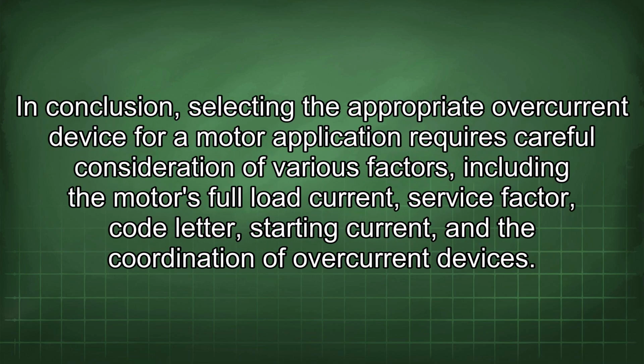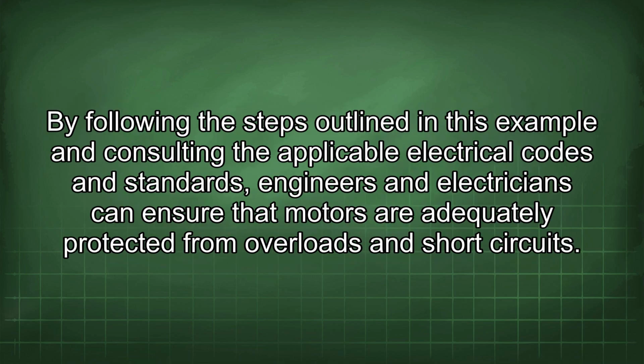In conclusion, selecting the appropriate overcurrent device for a motor application requires careful consideration of various factors, including the motor's full load current, service factor, code letter, starting current, and the coordination of overcurrent devices. By following the steps outlined in this example and consulting the applicable electrical codes and standards, engineers and electricians can ensure that motors are adequately protected from overloads and short circuits.